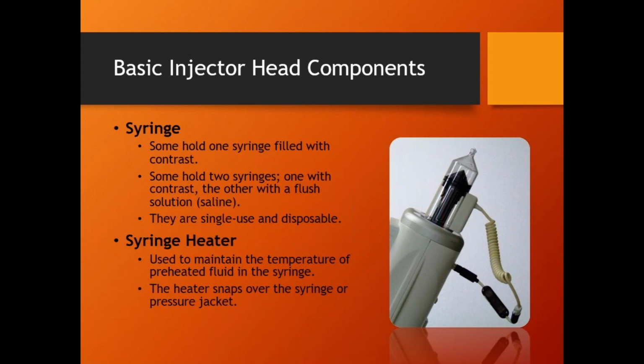So it doesn't really do any good to have contrast warmed up and then saline at room temperature, because as soon as you mix them, there was no point in warming the contrast up. So most of the time, if they're heating the contrast up, they're also heating the saline up, especially if they're shooting simultaneous shots.